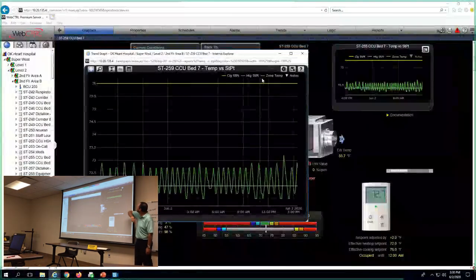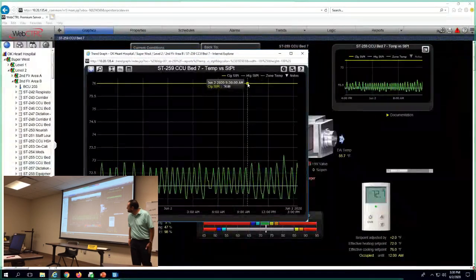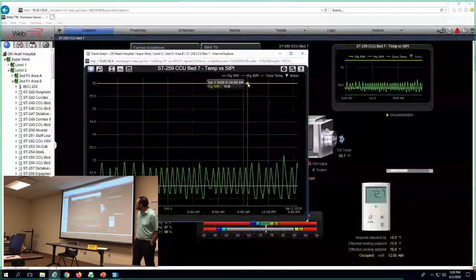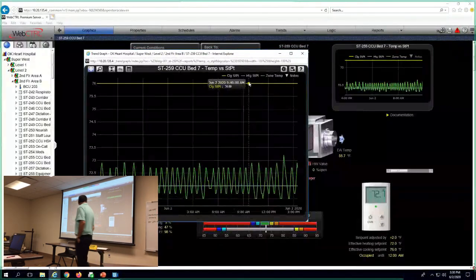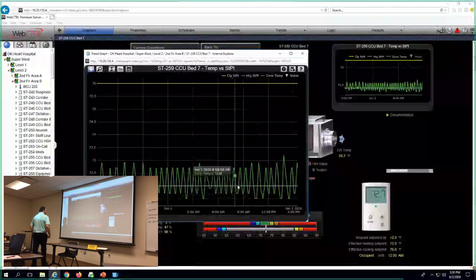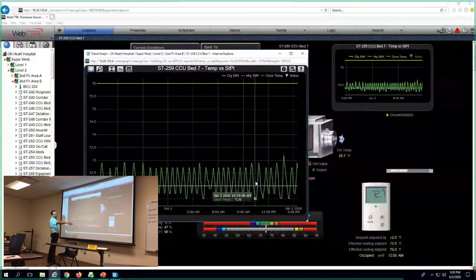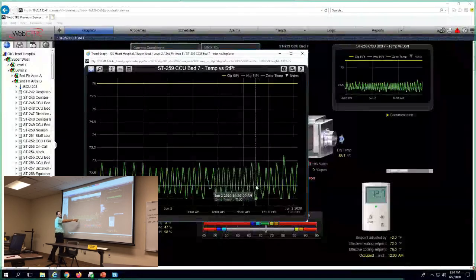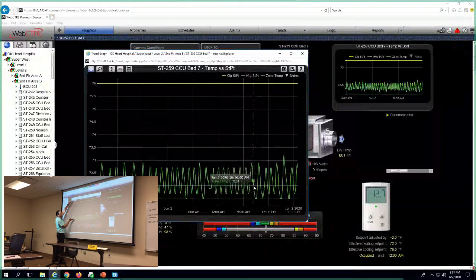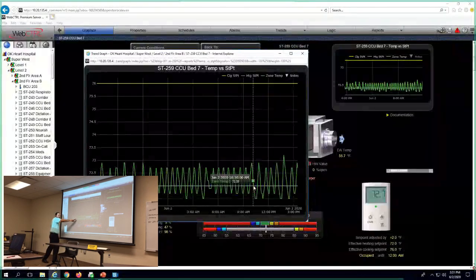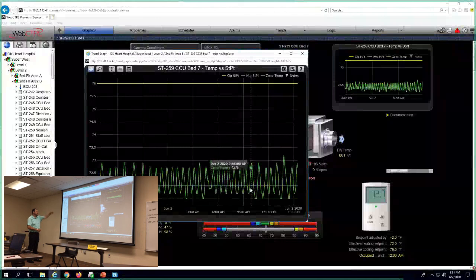Yes, it's super useful, but it's also somewhat confusing, because when I look at this, I see the set point's 76, which is the effective cooling set point, and we're riding around 72.9. Well, we're heating the space up too, because there's a 4-degree deadband between heating and cooling, and we're trying to maintain that heating set point. So it's warming the space up to maintain that heating set point. We've never gotten warm enough to go up this high yet, because we're in between heat and the deadband all the time. That's what's happening on those. So we don't ever end up all the way up there.